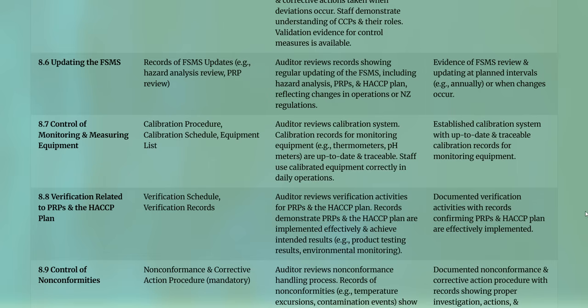Then clause 8.7 requires control of monitoring and measuring equipment. Here, you must have documents of calibration procedures, a calibration schedule, and a document for the equipment list. All this must be reviewed by the auditor during stage 1. The auditor will review the calibration system and calibration records for monitoring equipment, for example, thermometers or pH meters, and will confirm that all are up to date and traceable. During stage 2, staff will be observed to confirm that they use calibrated equipment correctly in daily operations. Your deliverables here: you must have an established calibration system with up-to-date and traceable calibration records for monitoring equipment.